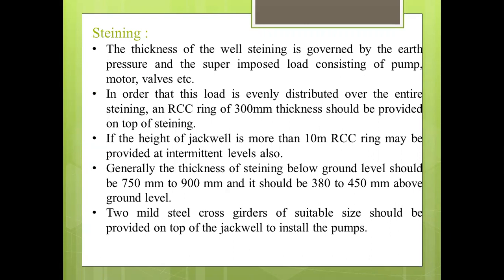Then the steining. The thickness of the well steining is governed by the earth pressure and superimposed load consisting of pump, motor, and valves. This load is evenly distributed over the entire steining. An RCC ring of 300 mm thickness should be provided on the top of the steining. If the height of the Jackwell is more than 10 meters above the ground level, the RCC ring may be provided at intermittent levels also.